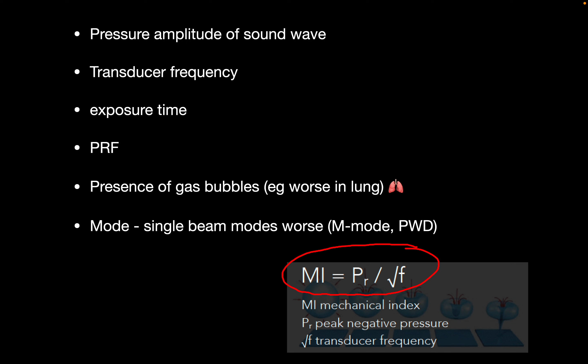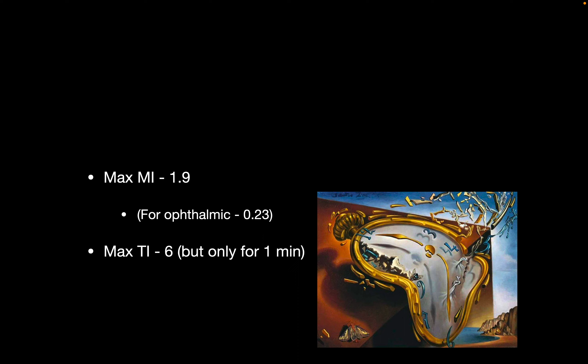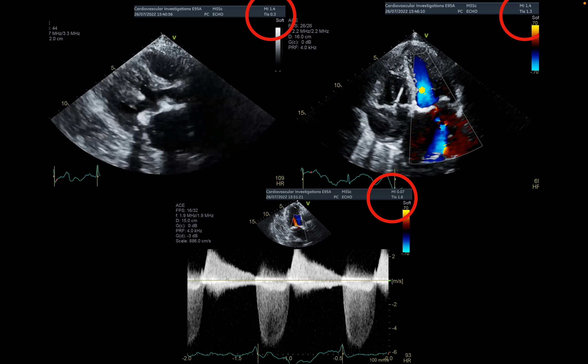So standards describe the maximum allowable mechanical index, which is 1.9, and it's going to be depicted on your picture. Much less for ophthalmic uses, and the maximum thermal index would be 6, but that's only allowed for about a minute, and this becomes more important in TOE imaging, really, where the ultrasound is very close to the tissue. If you use too much color flow or pulsed wave Doppler, you might get a warning from your system that you need to stop using the color for a while. The mechanical and thermal index is usually depicted on your image, and you really have to pay attention to these numbers.